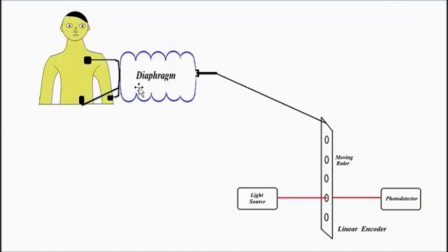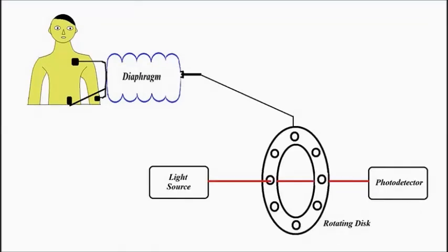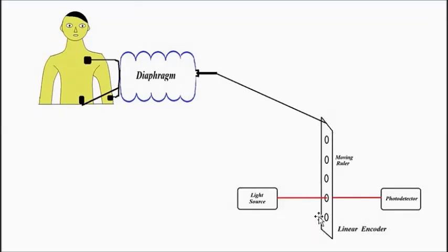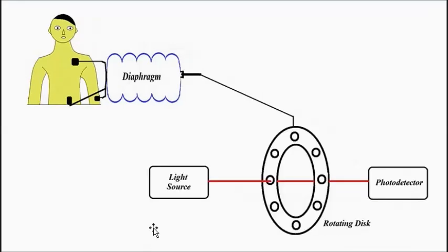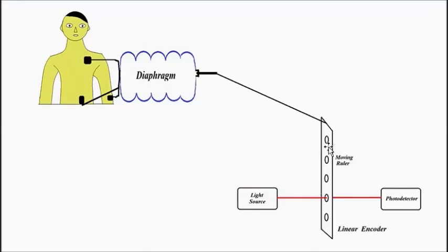So what happens is that the diaphragm that is connected to the body part where pressure is to be measured, so when pressure fluctuations happen at a specific part of the body, let's say blood pressure, the diaphragm undergoes compression and expansion. This in turn causes the ruler, the disc or the ruler, to move, either to rotate or to and fro movement.